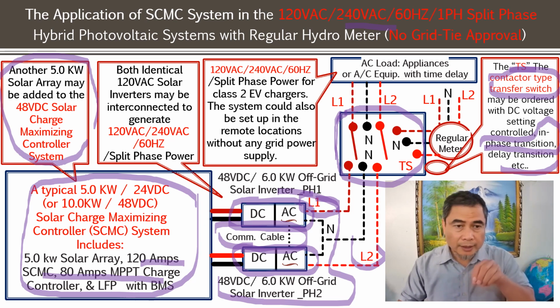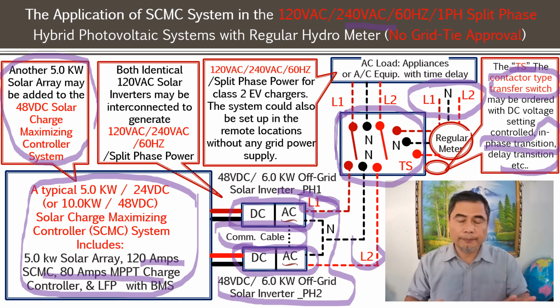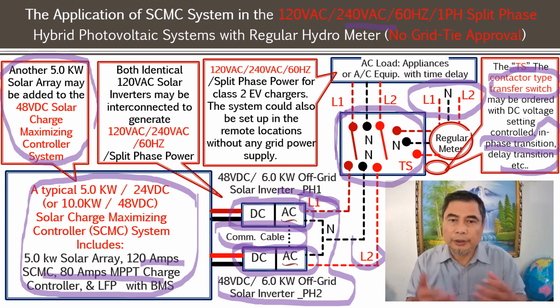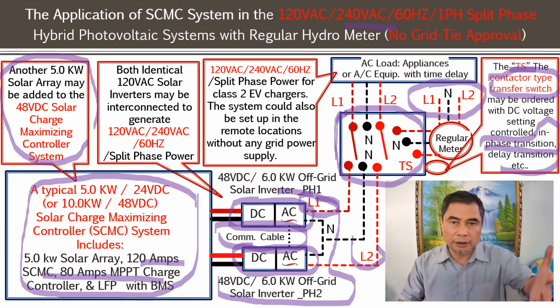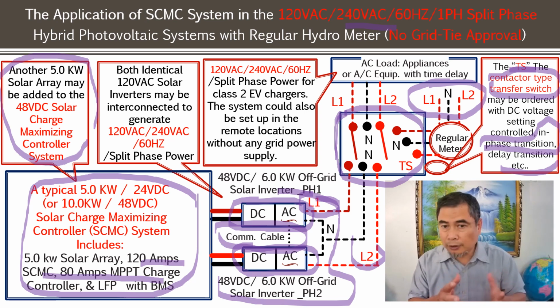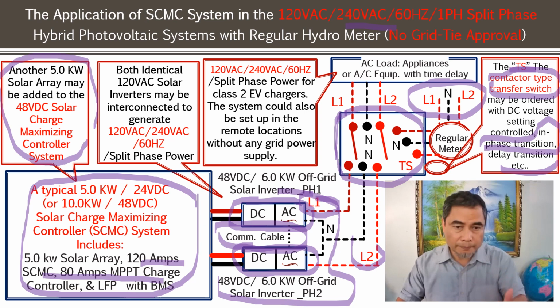Just to introduce this application, you know that the solar charge maximizing controller can be used for this split phase application, which is very popular in North America, where you have a 120/240 split phase system for any residential house. Cottages depend on how big the property is. You can build this solar array and install it on the roof, or install it rack mounted. Some commercial buildings also use split phase supply, and you can put them on the roof. A flat roof can have quite a lot of solar array built in, and you can make the class 2 EV charger available for customers or for your employees, even for business application.